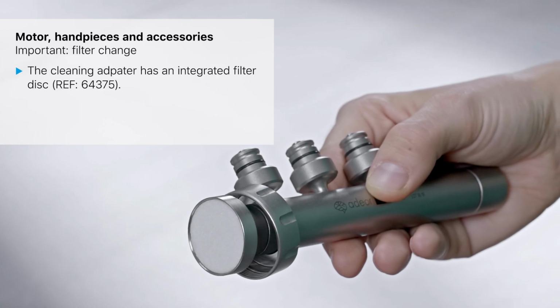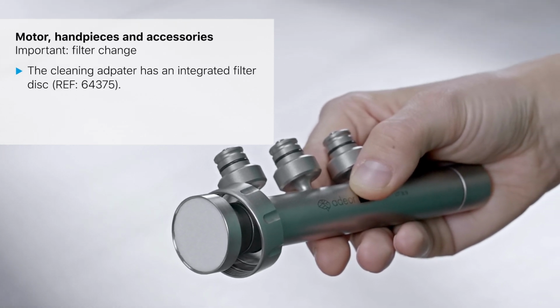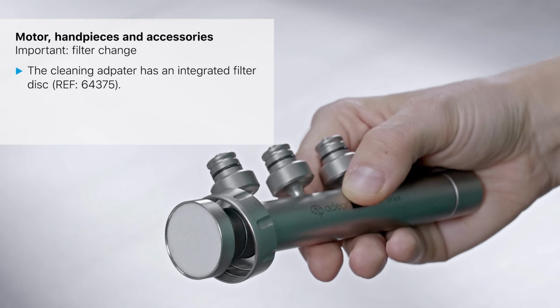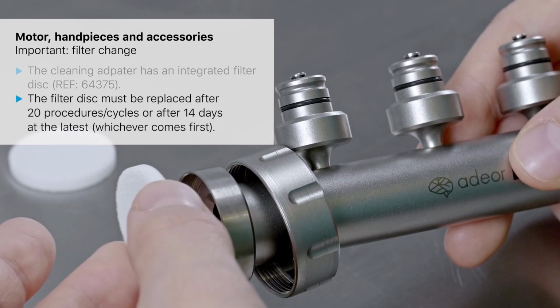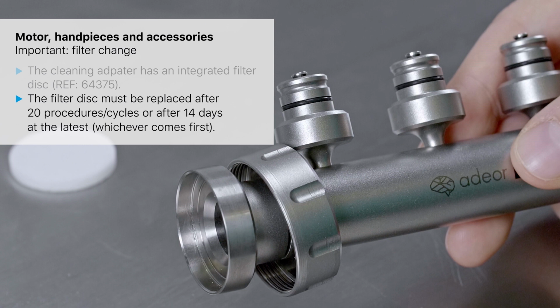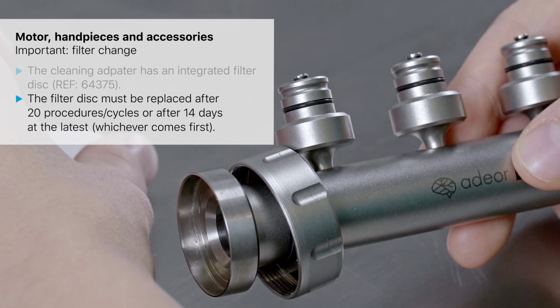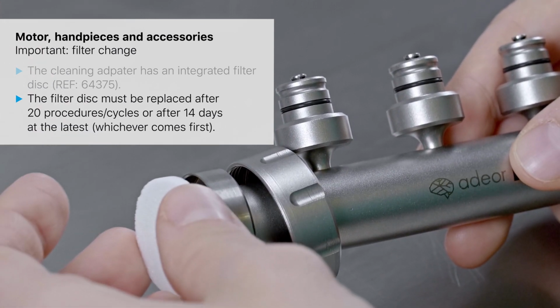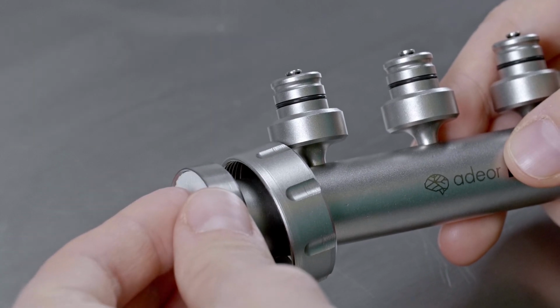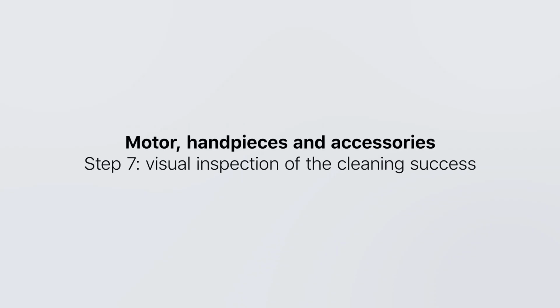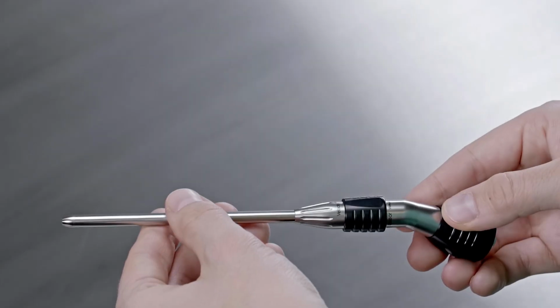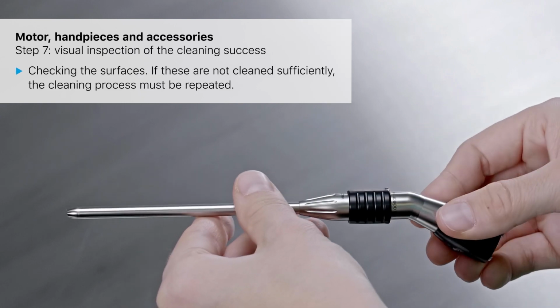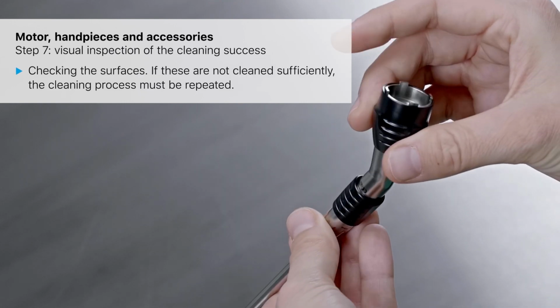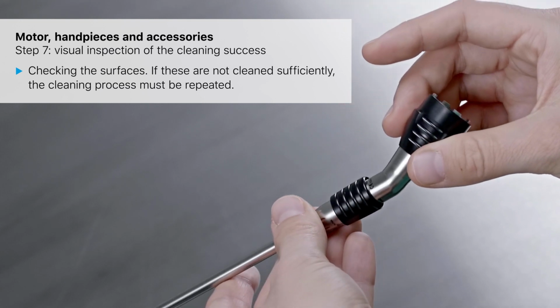The cleaning adapter has an integrated filter disc, reference 64375. The filter disc must be replaced after 20 procedures, cycles, or after 14 days at the latest, whichever comes first. Checking the surfaces. If these are not cleaned sufficiently, the cleaning process must be repeated.